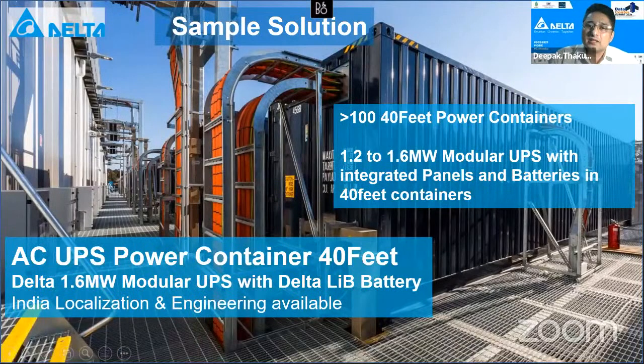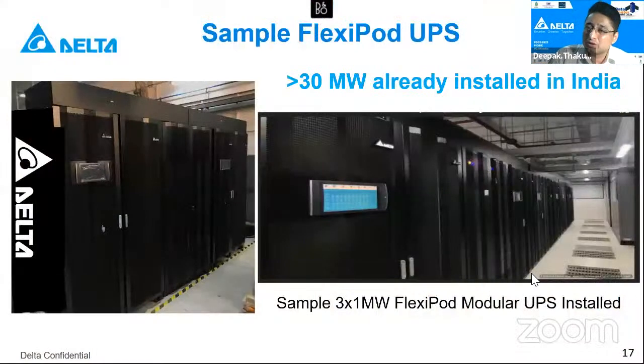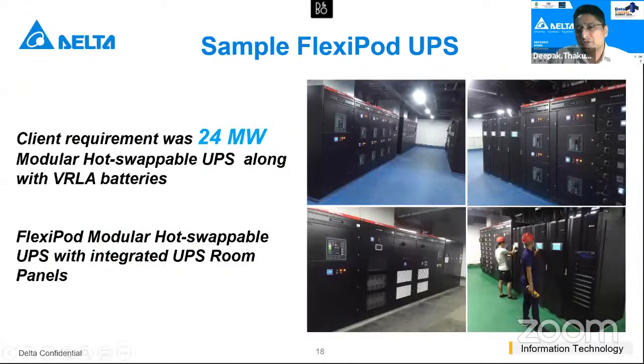And then we also did a flexible architecture for existing setups, where we managed to fit in 3 megawatts of UPS system into the space where traditionally you could not have fit 2 megawatts of UPS system. So this is how you can see the real site pictures, which we have helped our customers to optimize and create more. Similarly, 24 megawatts deployed.